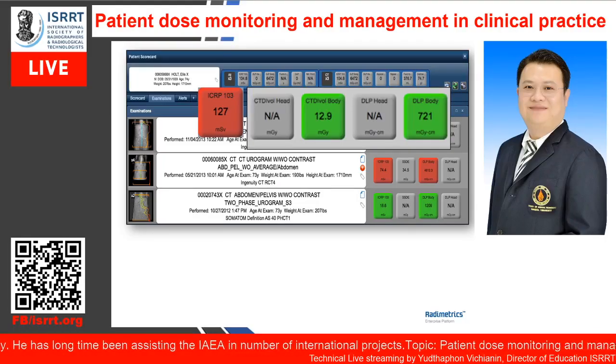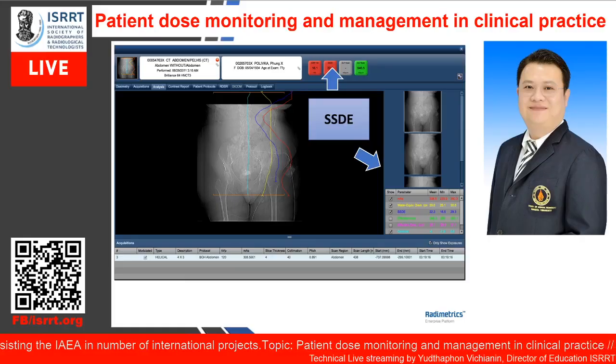In general, these figures we can directly extract from the DICOM header. But if you want a more precise calculation of the dose to an individual patient, note that the dose you see from the DICOM CT dose sheet is mainly phantom dosimetry, not patient dosimetry. As I said, there are two sizes of phantom, PMMA phantom 16 and 32. Mainly each year physicists will come and do the measurements for the CTDI.